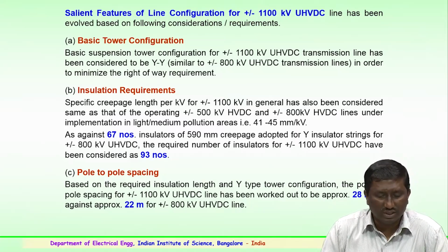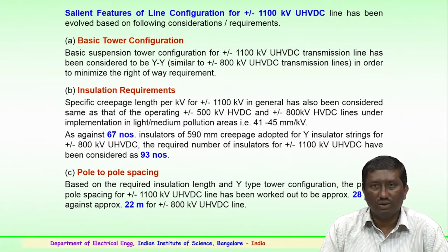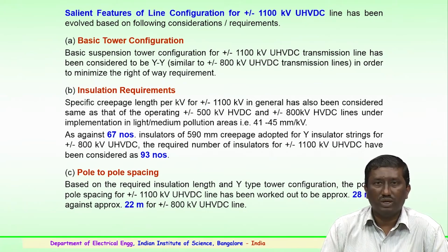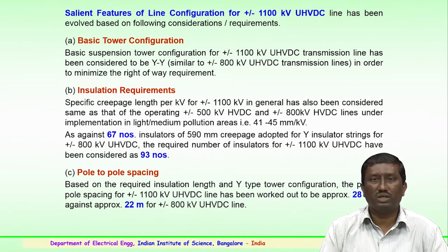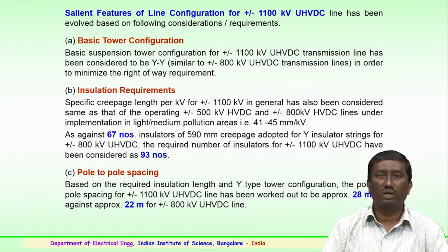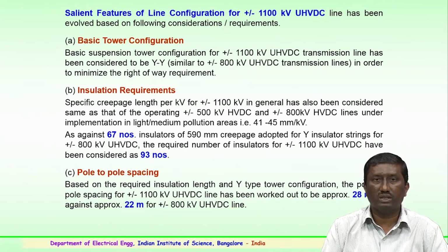So, the salient features of the 1100 kV UHV line have been evolved based on some requirements. What are the basic requirements of a tower configuration? The basic suspension tower, particularly for 1100 kV ultra high voltage DC transmission, should be of a YY configuration similar to plus minus 800 kV which is presently being used. This will minimize the right of way requirement if we go in for this Y type of configuration.